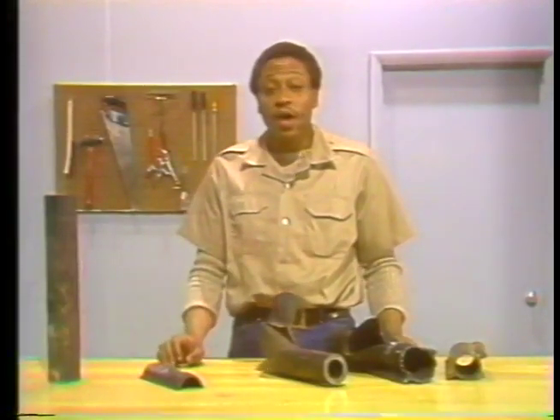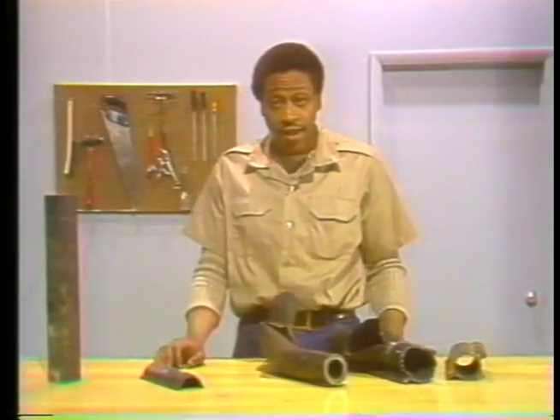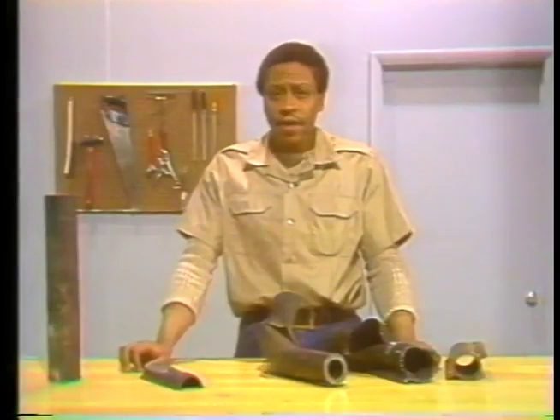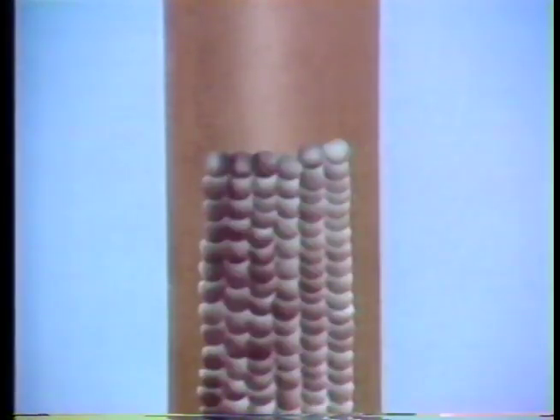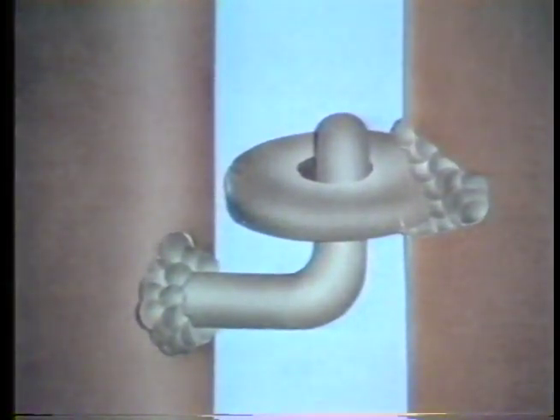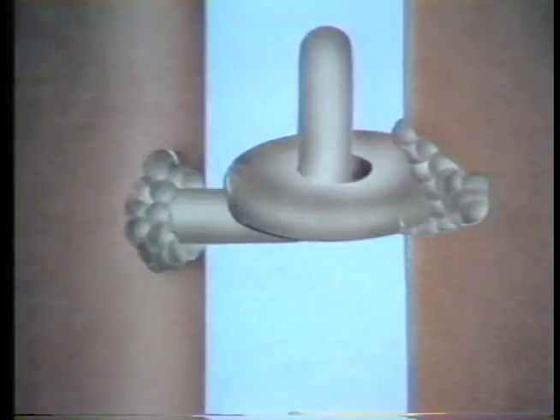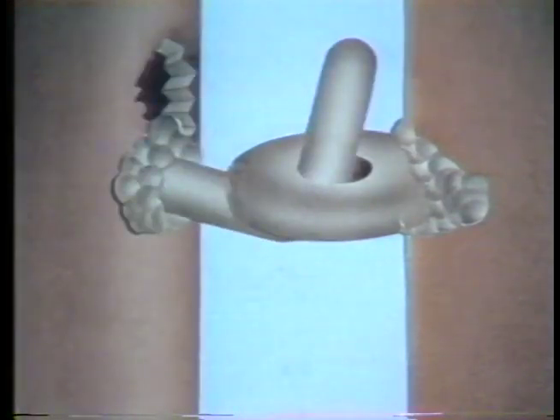Three more failures you may encounter are fatigue cracks, tearing of tube metal at weld patches, and tearing of tube metal at support clip attachments. Fatigue cracks are caused by mechanical stress and appear as clean, bright breaks through the tube. Tearing at weld patches also results from mechanical stress — when the weld patch and tube expand or contract at different rates, the contraction can stress the metal so severely that it tears open. This kind of failure can indicate that the wrong material was used for welding the patch. Tearing at support clip attachments is also caused by expansion and contraction; if tubes held by support clips expand or contract unevenly, a tube may be torn open where the clip is welded.